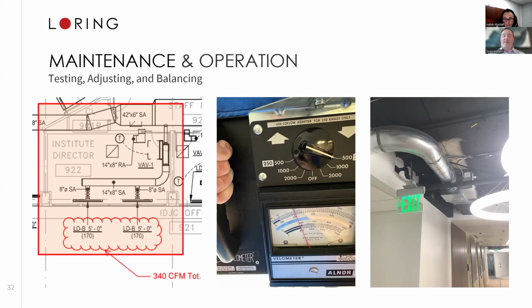But in this case, and this is more common practice in laboratory buildings and healthcare buildings, we're starting to recommend a regular period of testing, adjusting, and balancing in a building, so that we can make sure that these things, which do drift out of calibration, maintain that calibration through the life of the equipment.